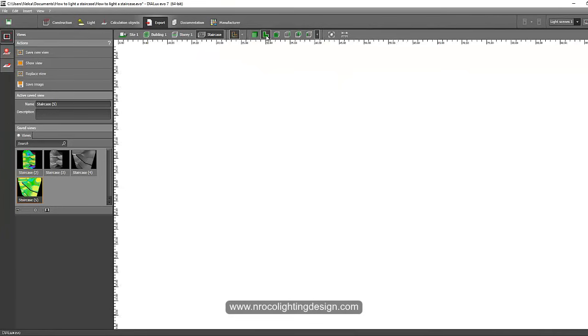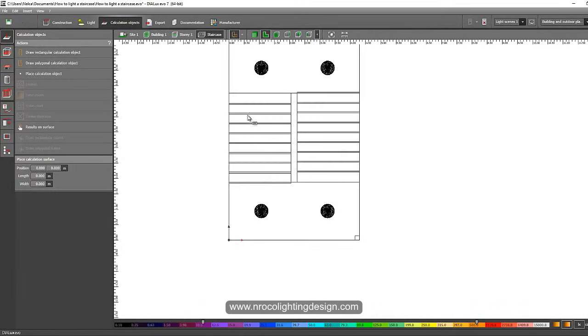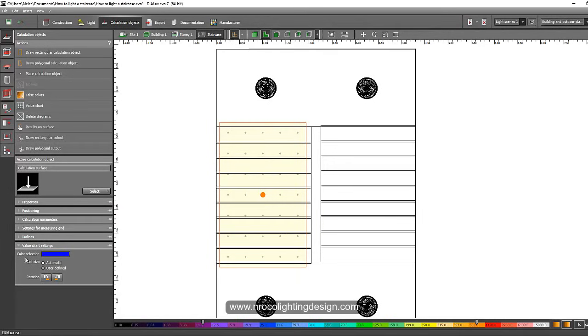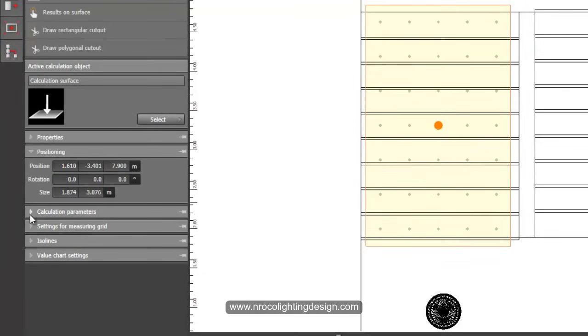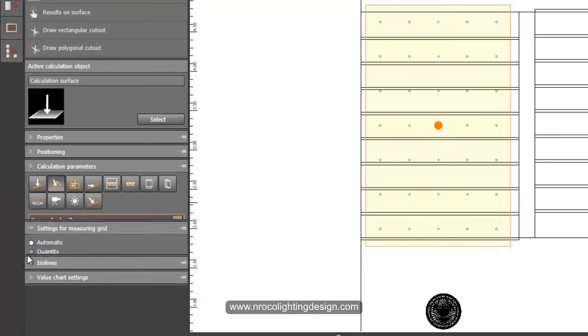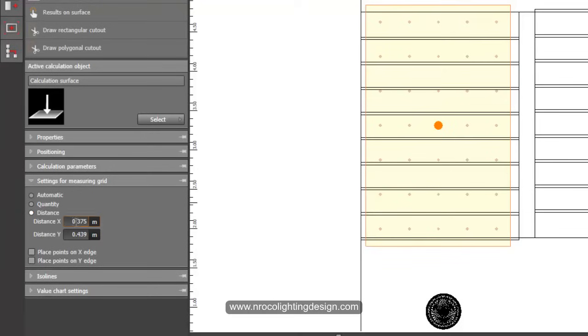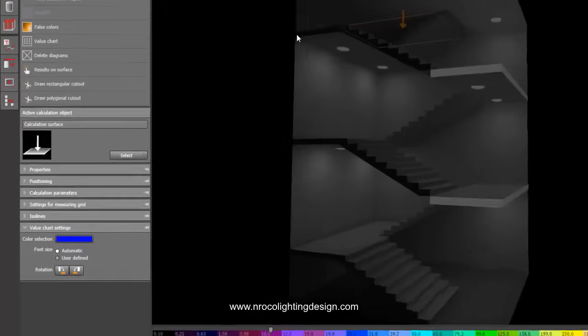Go to Plan View, then Calculation Objects, and select 'Rectangular Calculation Object.' It should be set as a Surface. In properties: Calculation Surface, Positioning, and under Parameters make sure it's set to Perpendicular. Set the measuring grid distance to 0.5 by 0.5. Now you have one calculation surface placed.